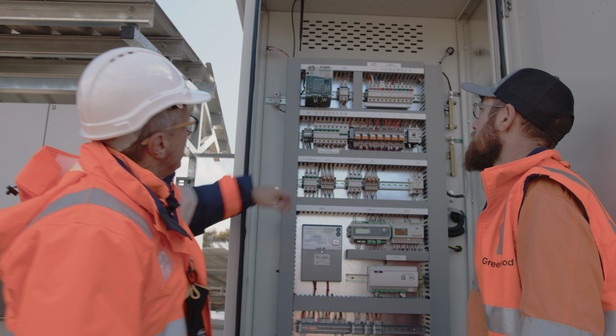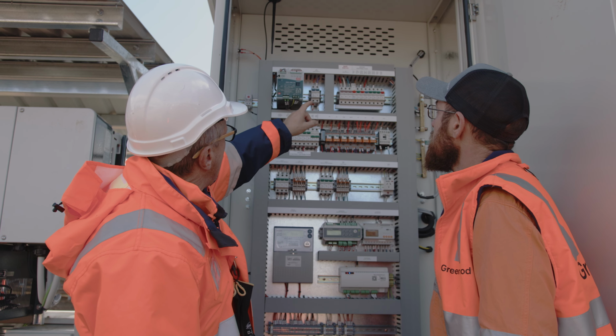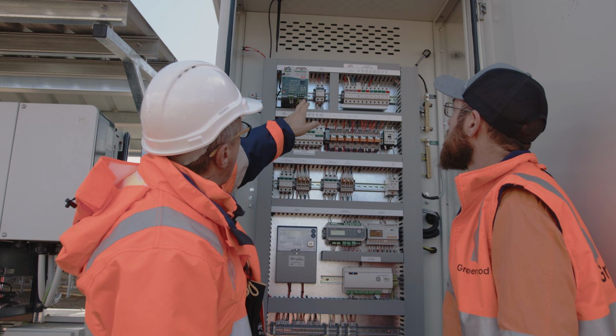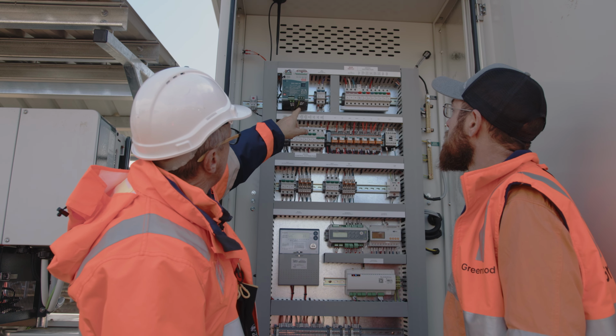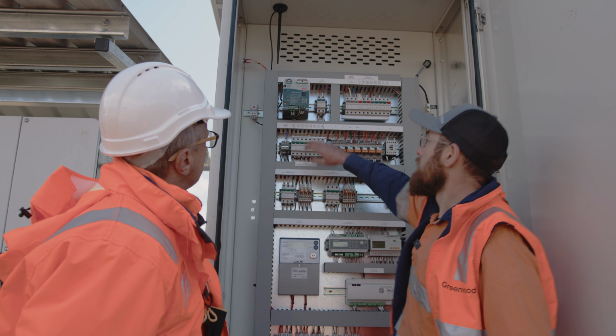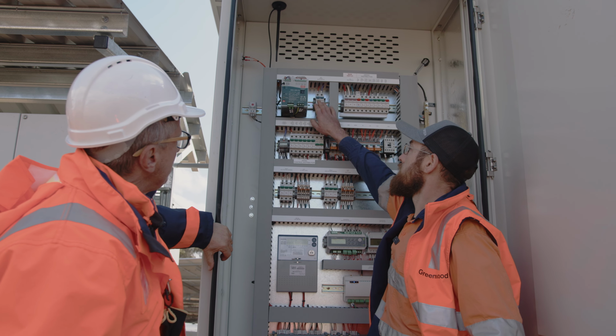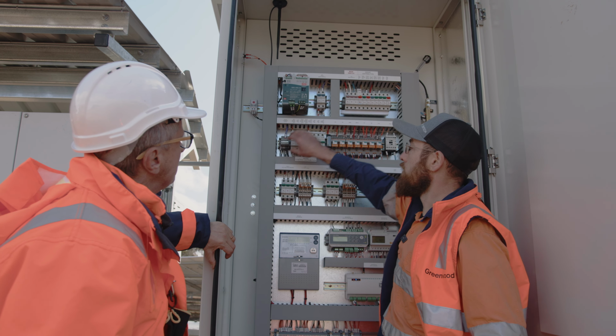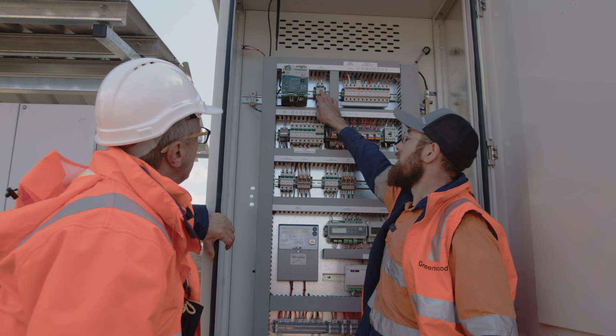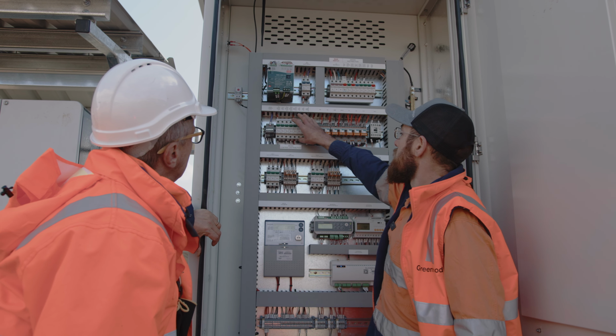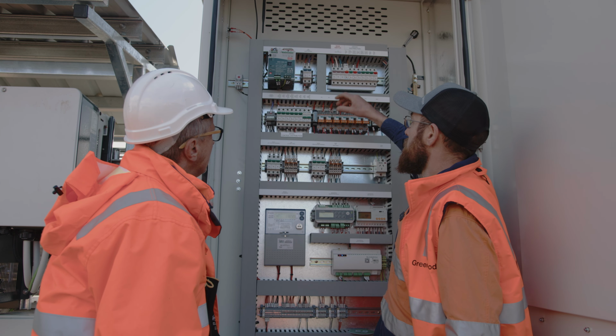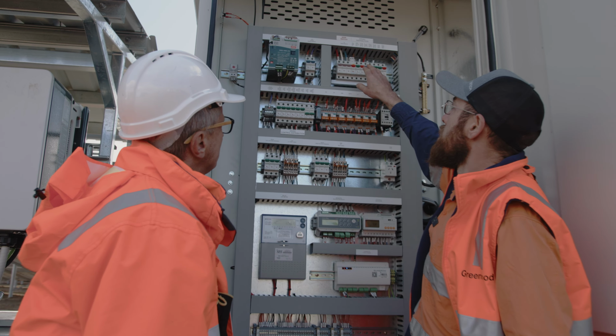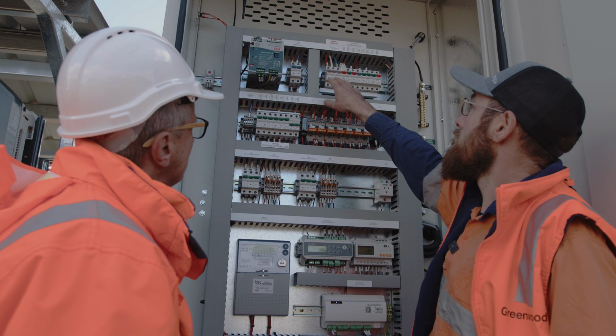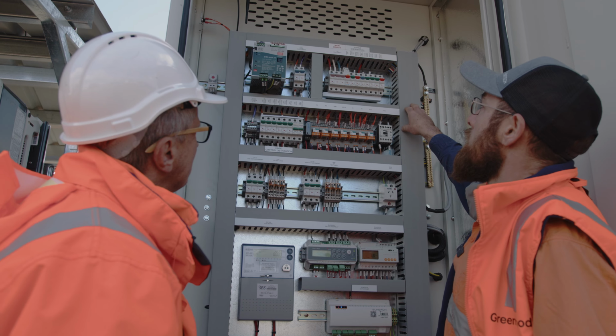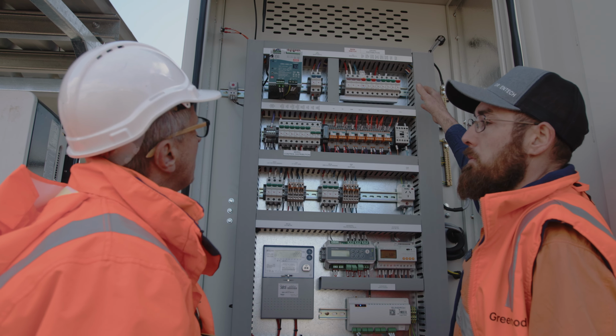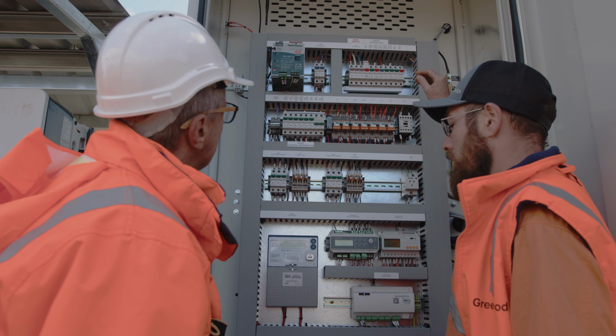Excellent. Now, moving from left to right, you've got the AC main switch and the 24 volt DC main control. Can you just... Yep, so the power from this power supply is fed to this circuit breaker, so you've got a point of isolation at any time for the below 24 volt distribution. That's just offering protection to that system. We have several 24 volt components in here. To the right here, we've got the 230 volt distribution section, which takes our 3-phase, and we've got a few loads coming off that for controls specifically of the main breaker, grid protection, and charging the batteries.